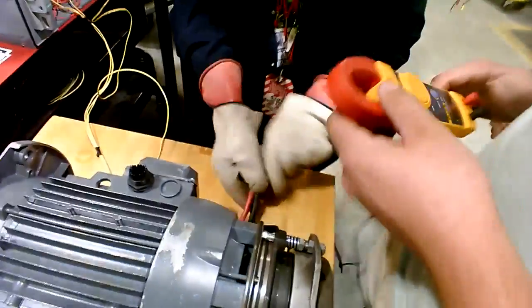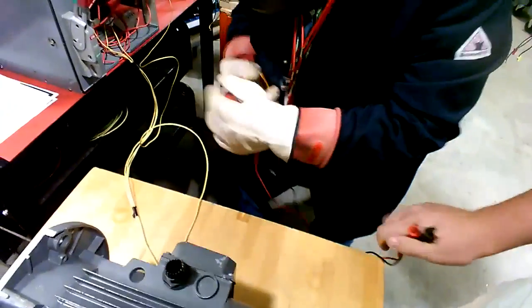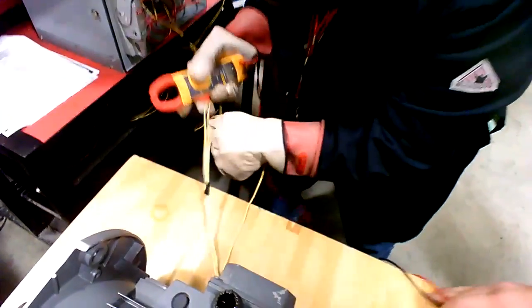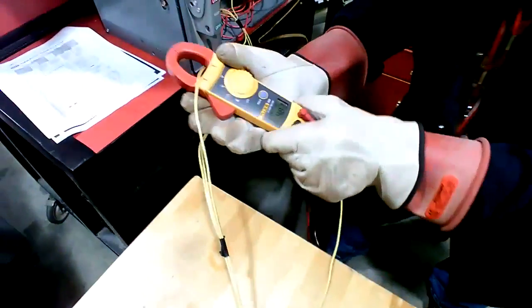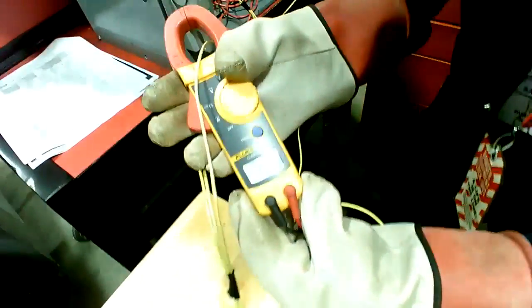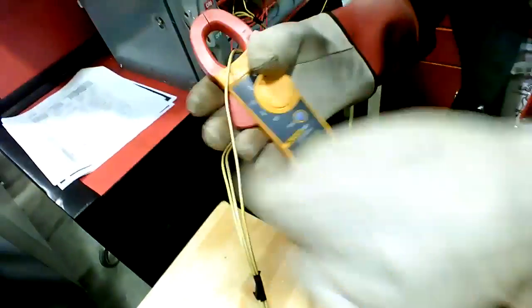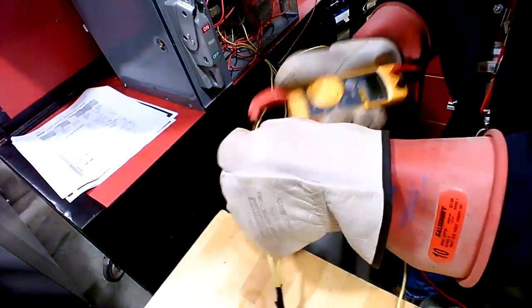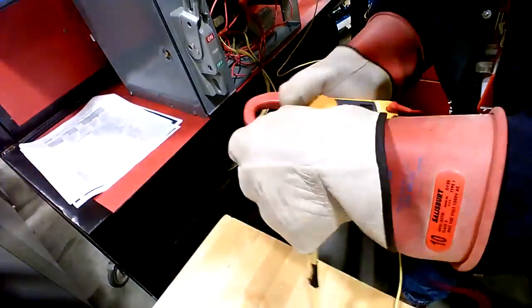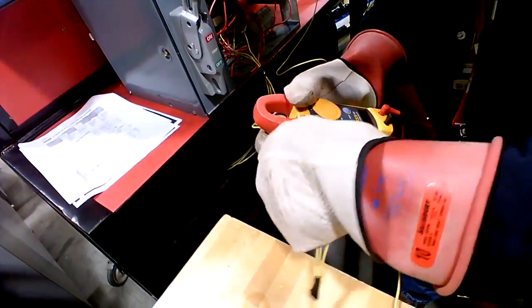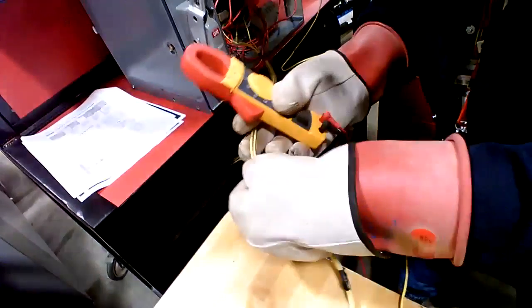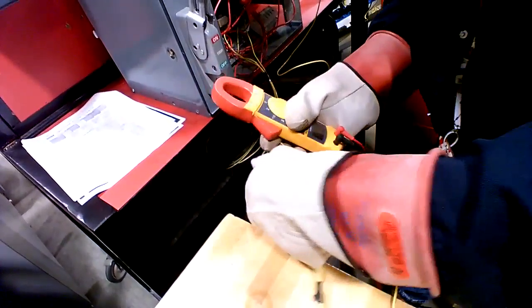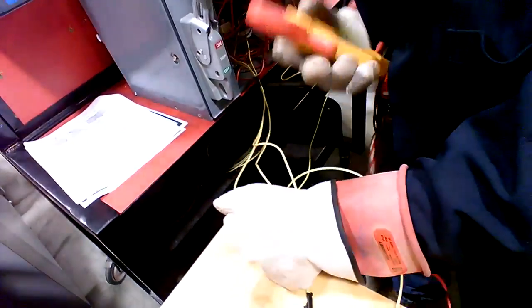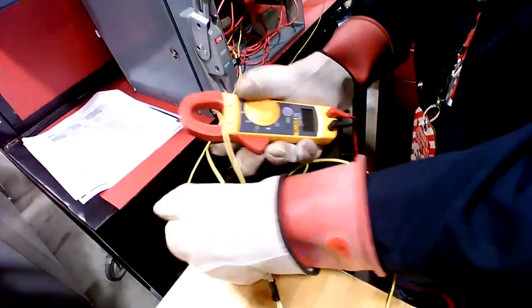Okay. So now the next thing is we're going to switch it over to amps AC. And we're going to read around each phase conductor going to the motor. And we're getting 4.79 amps for that leg. When you're checking amps on the motor, you get one phase conductor at a time, one at a time. Let's separate it good again. We go back again. Make sure I get all three of them.